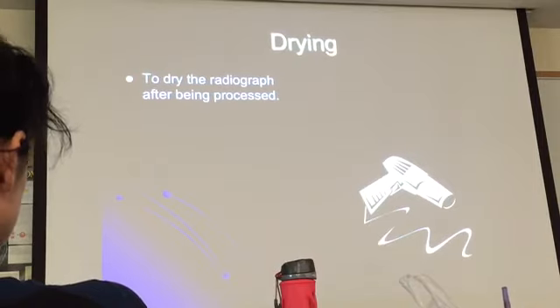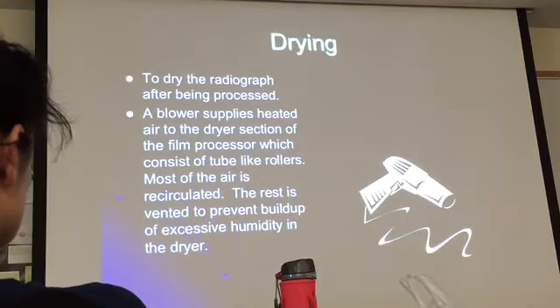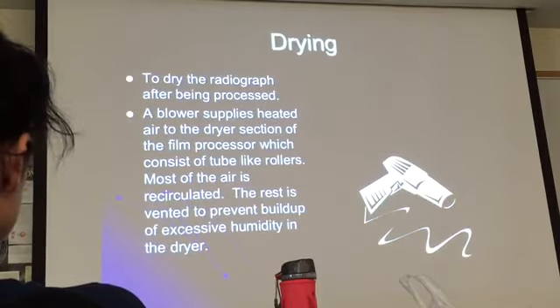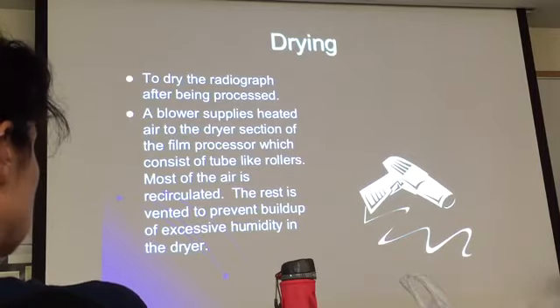Drying — it's just like drying your hair. It's a big blower that blows hot air. It is used to dry the film. The blower supplies heated air to the dryer section of the film processor, which consists of tube like rollers. Most of the air is circulated; the rest goes out the vent to prevent buildup of excessive humidity. It's important to keep the vents open.